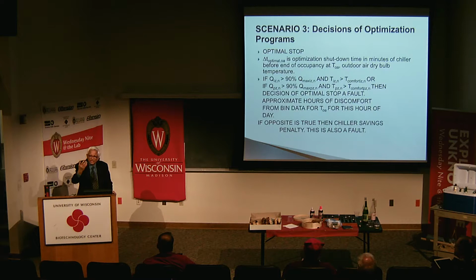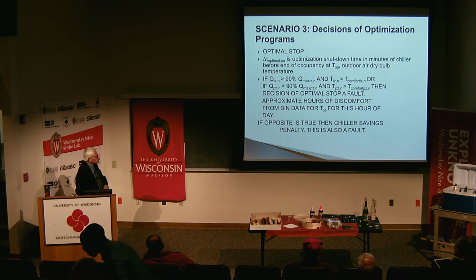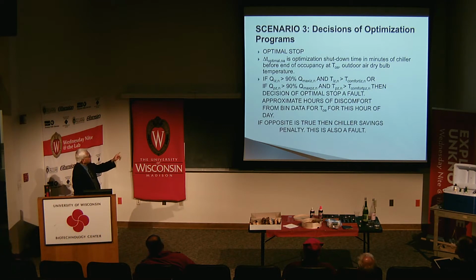If you look at the outdoor air temperature, weather stations sometimes give you data in 3-degree intervals. Then you can calculate the bin interval of that temperature, and for the entire cooling season accumulate so many hours of discomfort that occurred for that outdoor temperature, and start accumulating for every outdoor air temperature that occurs at that time. So that's the penalty. And if the opposite is true, suppose before the optimal stop time the temperature is satisfied, then you know that you have a chiller savings penalty.